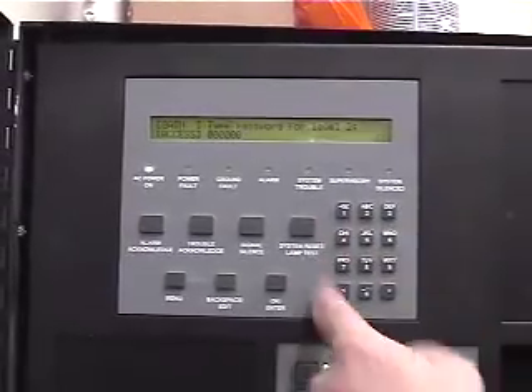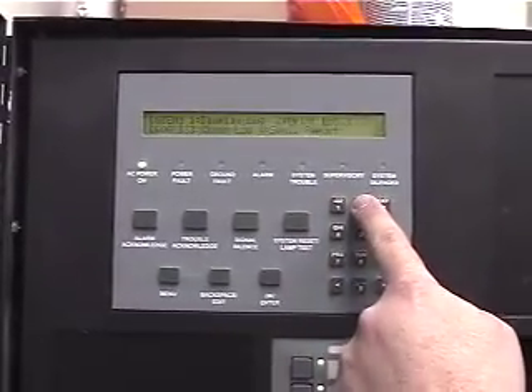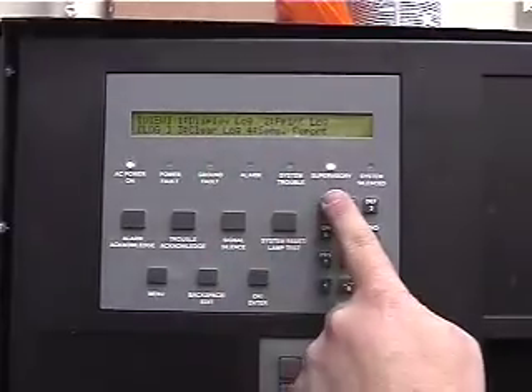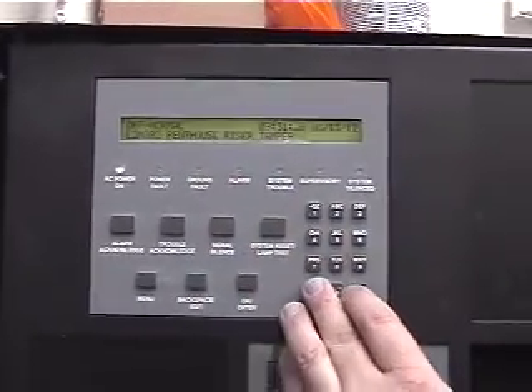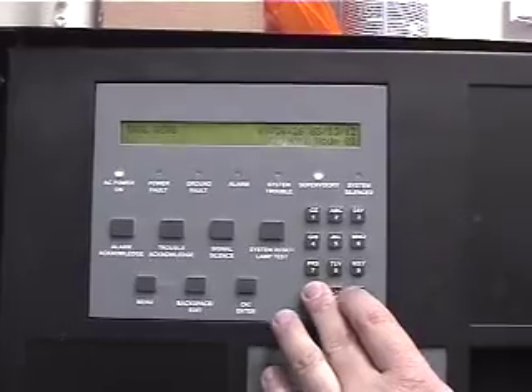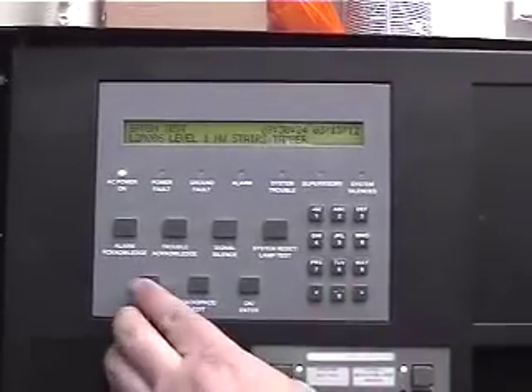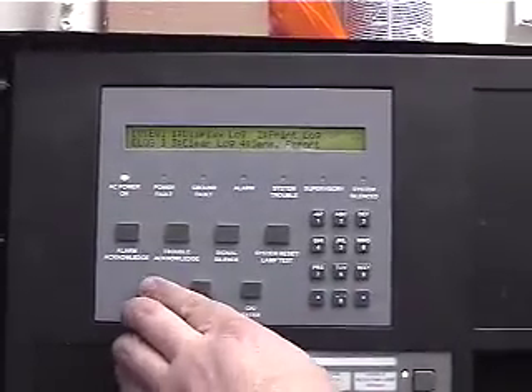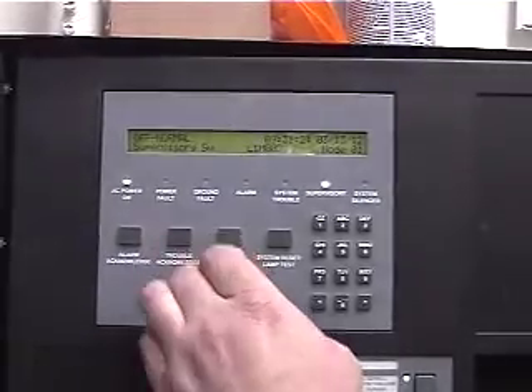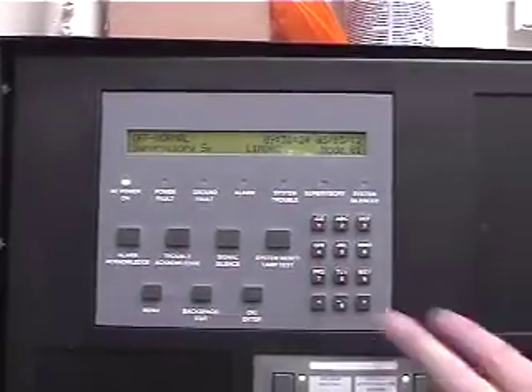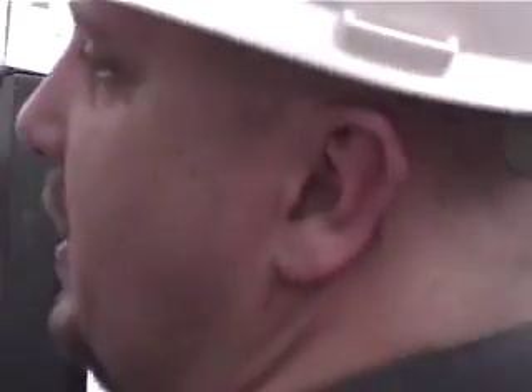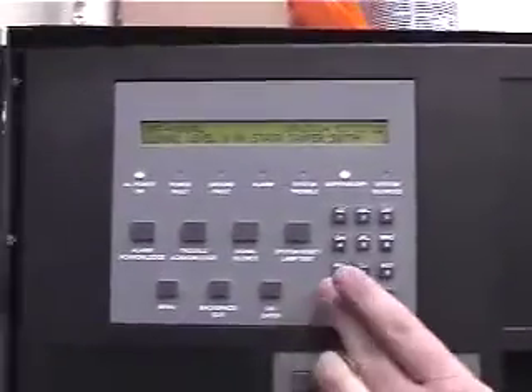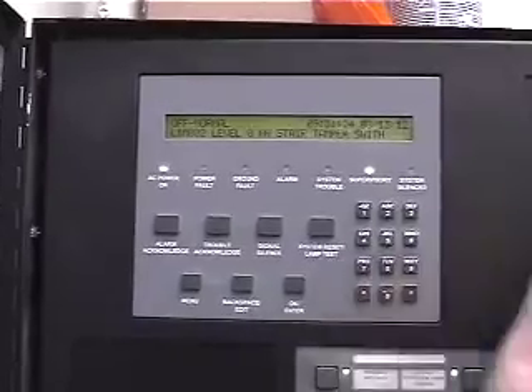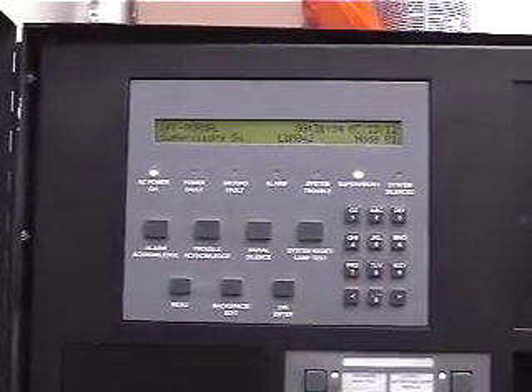You could say 6 for log, level 2 password, come in, and you can say display log 1, and you can go through and just go through the whole, I think it's like 1,000 memory log. Also, if the panel is in normal condition, you don't have to go in the log, you can just start pressing the arrows, but it'll only allow you to do that when it's normal. So if it's normal condition, you don't have to actually go in and display the log, you can just start pressing back button, and it'll start going through the log.